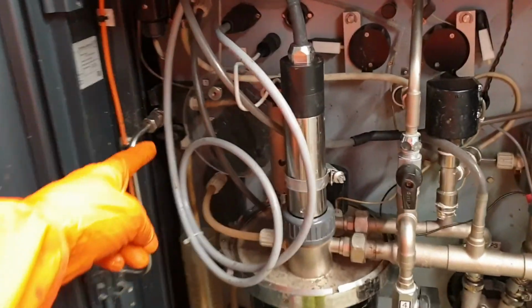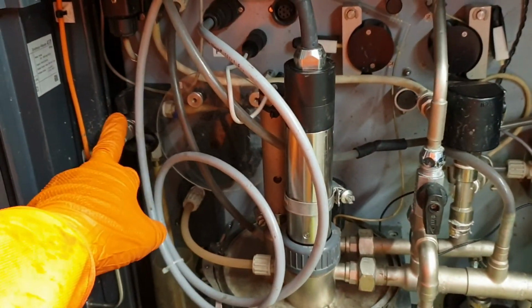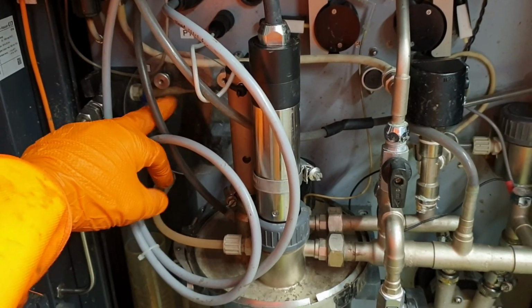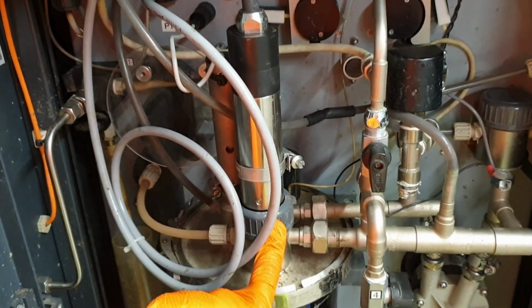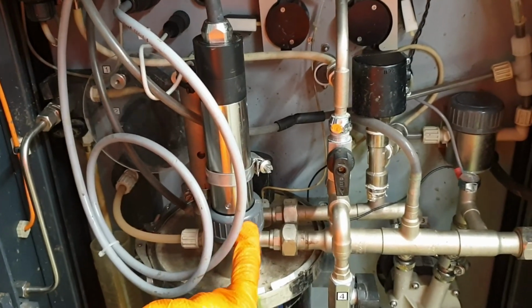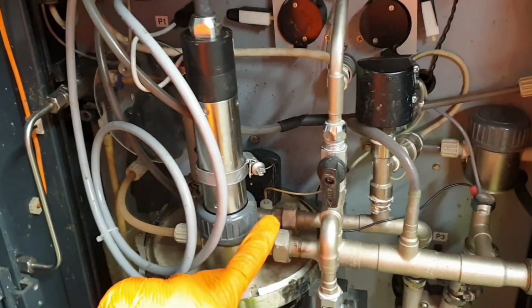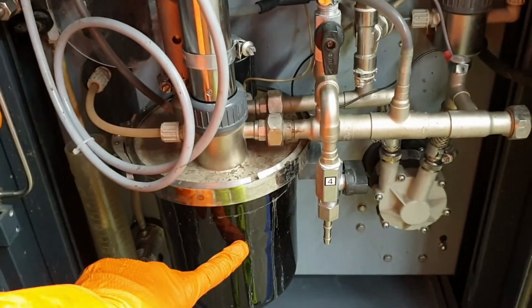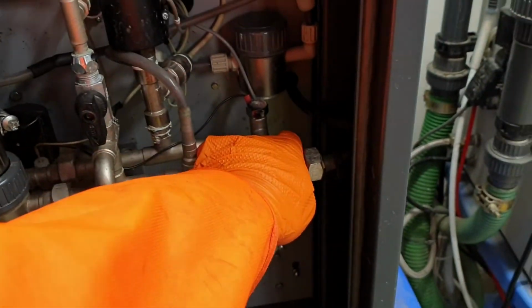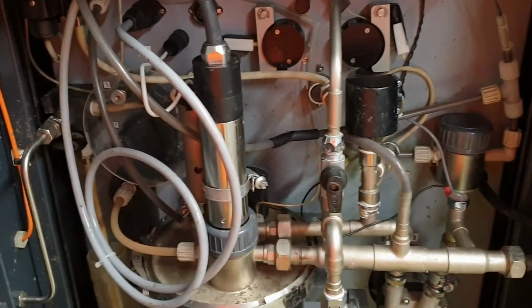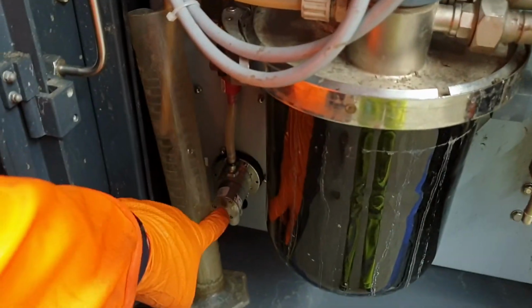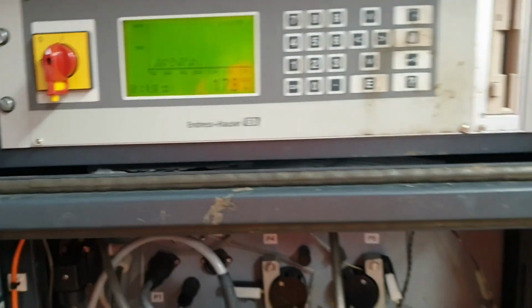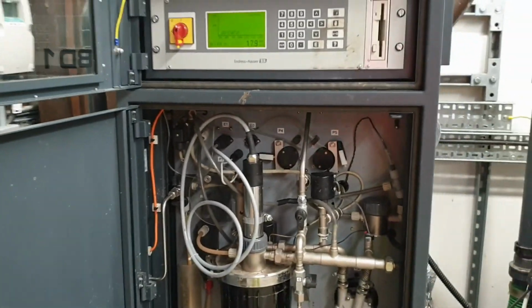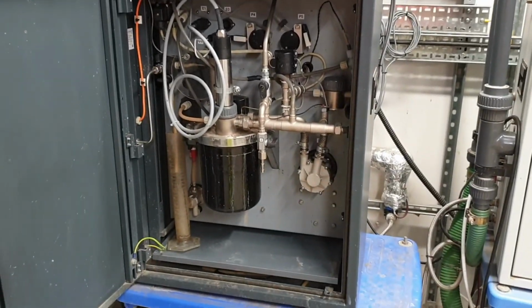With these, it's basically checking the filter's clean, you're getting samples through into the analyzer, you haven't got any problems with the pump tube. This is calibrated every midnight, so you check the calibration figures are good. If not, clean it, change the end cap. Check the circulation's good, heaters are working correctly, and the calibration of the metering pump in the bottom left hand corner. If all of them are within specs and everything's working, that reading is right. Probably. But yeah, these are, if anything, the simpler analyzers I look after.